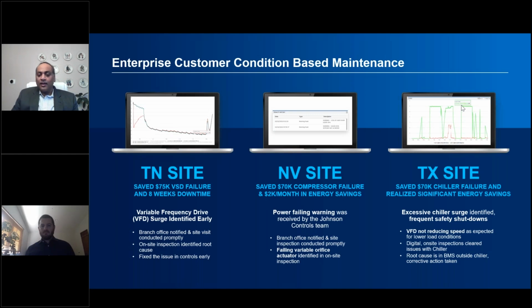On the second example, here's the warning code the chiller was sending, flashing on the screen, and that was again a very important alert our team caught on time. This was a power failure that was facility driven. Sometimes chillers are impacted by facility-related issues, power, water from cooling towers, all outside the chiller, but it does impact the day-to-day health and sometimes even energy performance of the chiller. Again, the team identified this quickly and corrected the problem.